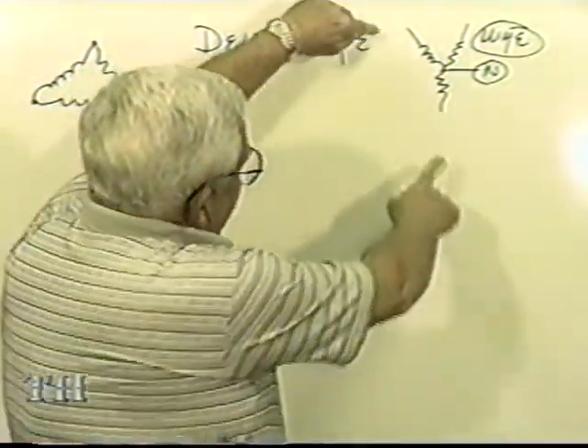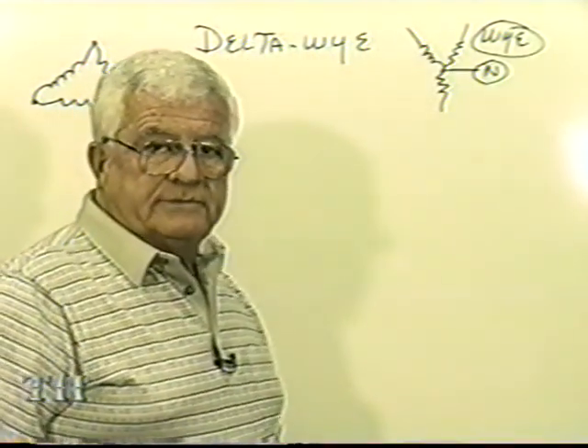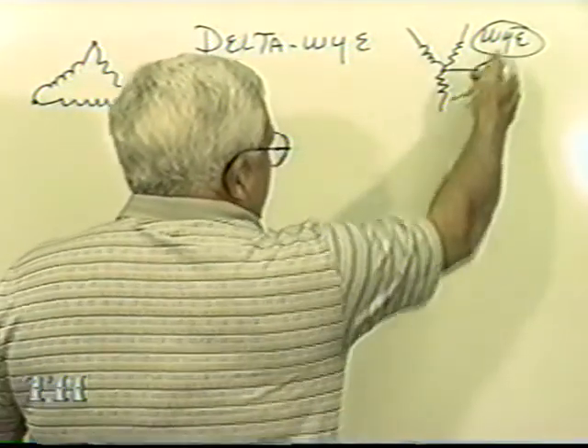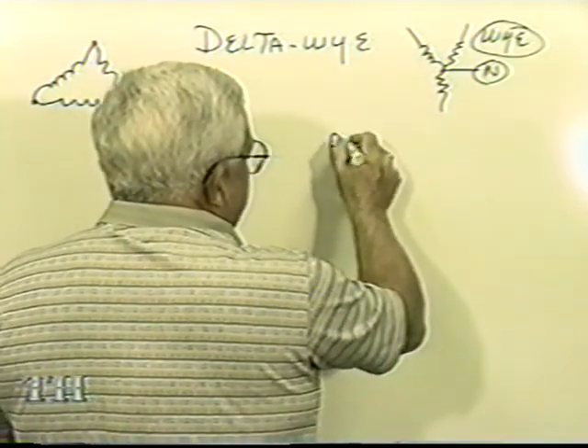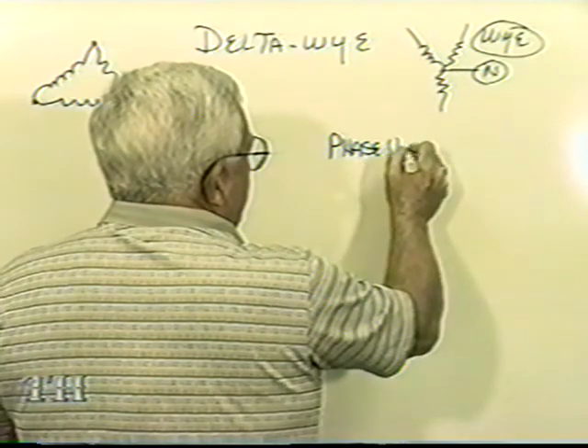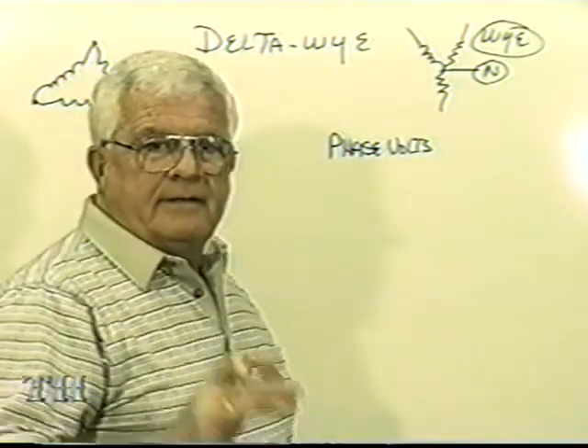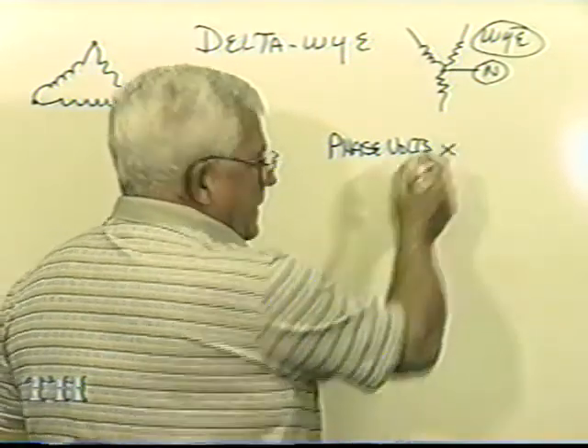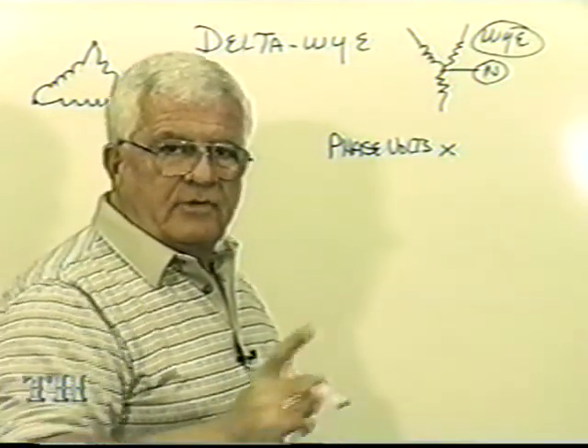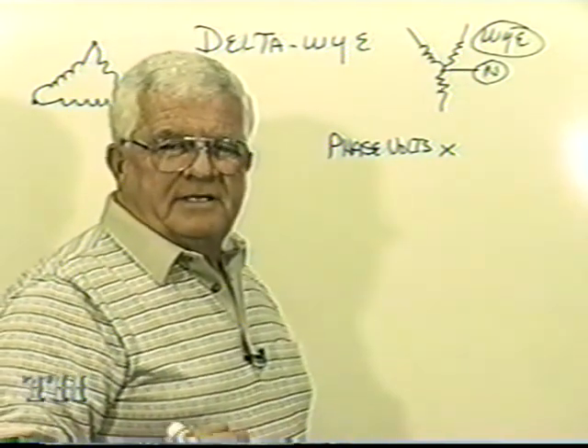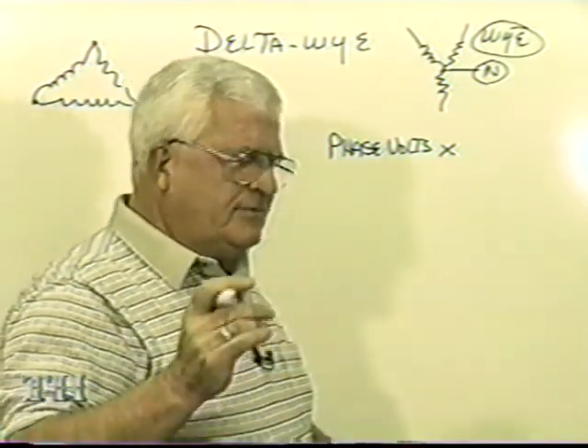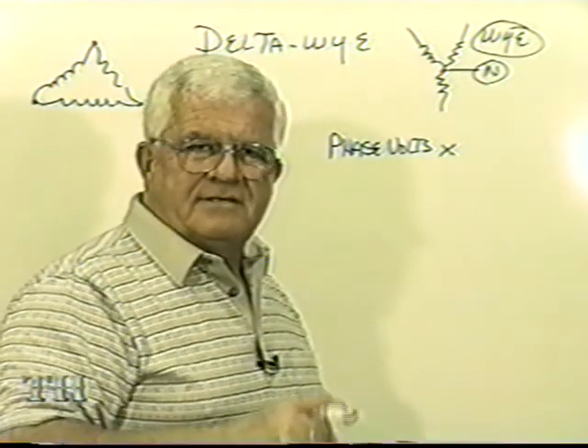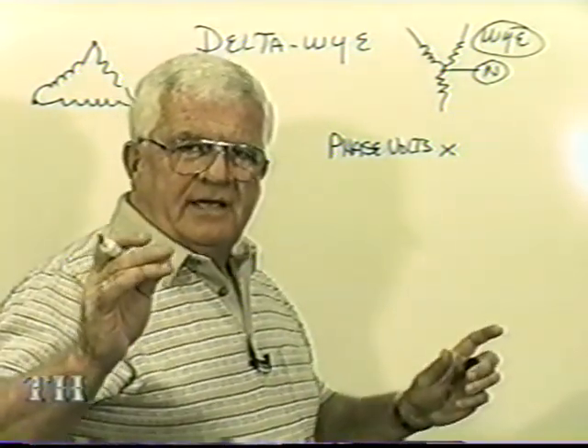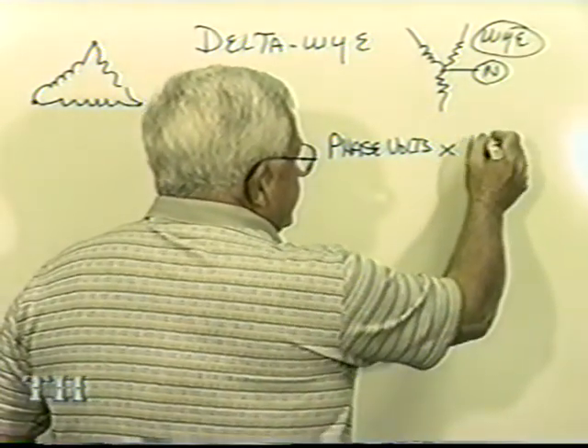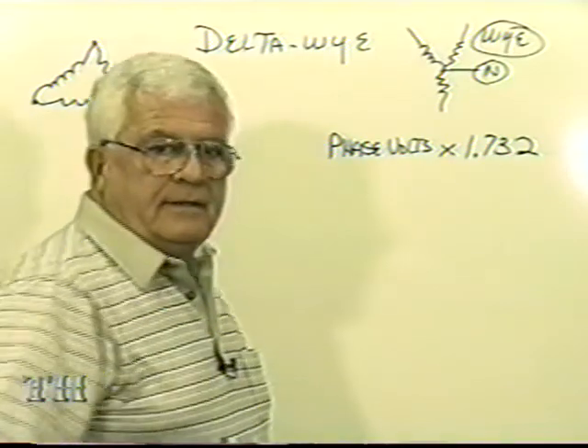If we put a meter from right here, you said it was 120 volts. And if we put a meter from here to here, it was 208 volts. Watch, our format for a Y is: if I take the phase volts times... here's the only number that I'm going to use, it's the only number I need. Some books you read, they got the 1.14, they got the 866, the 577, all kinds of numbers. I stick with this number right here: 1.732. That's all I need, and I'll answer the questions.